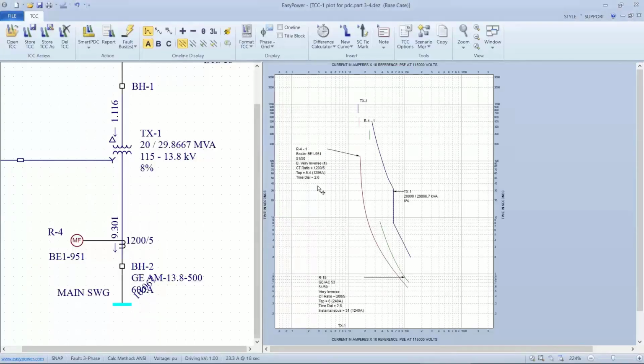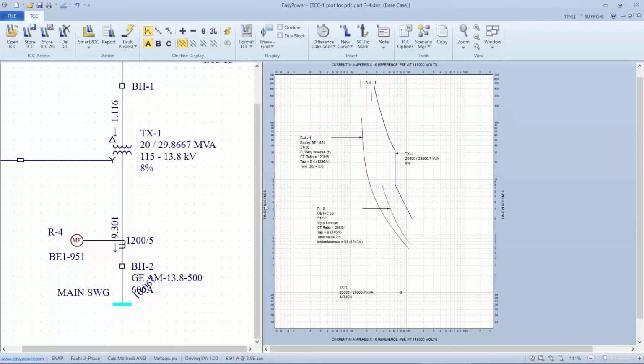Now, one other point to be made is that when we're plotting relays, we're plotting the response time of the relay itself. We're not showing the clearing time, because that involves the opening time of the breaker, which will vary based upon which breaker we're using. The tool will give us the ability to see what the minimum separation is between these two curves. If I select both, hold down Control and select both, and use the difference calculator, it will show us the minimum amount of time that these are separated, and at whatever current the difference will be, right? And so between a 5 cycle and an 8 cycle, this is an order of magnitude greater as far as the separation. So there's plenty of time for the one breaker to clear before the next relay is picked up.